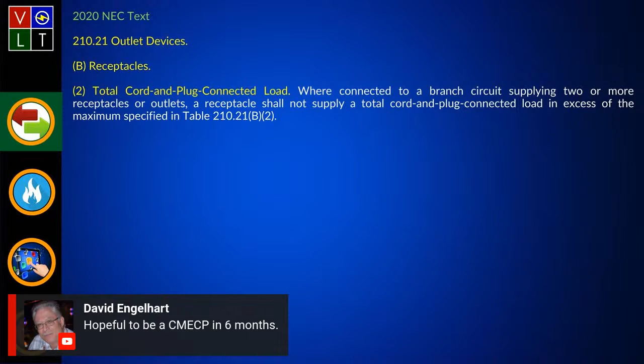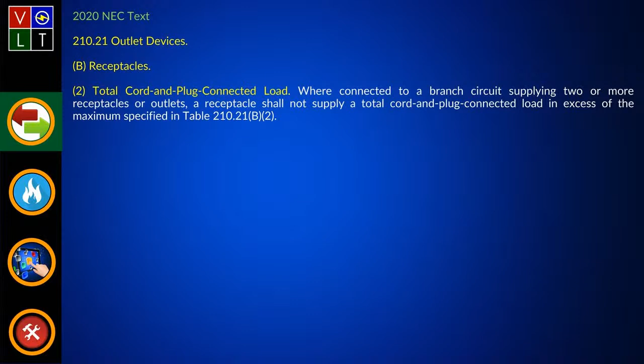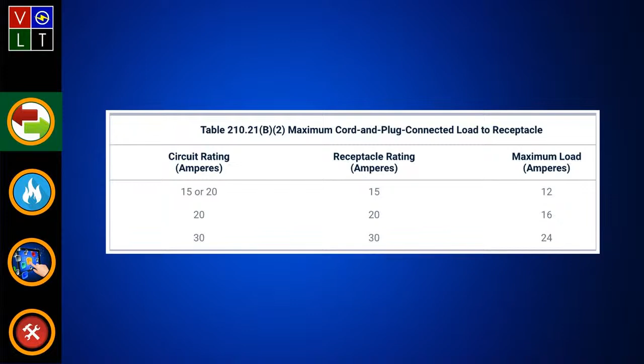What I decided to show here is 210.21(B)(2) and (B)(3). We'll talk about this. If you're talking about cord and plug connected, this is where you have a branch circuit supplying two or more receptacle outlets. It says the receptacle shall not supply a total cord and plug connected load in excess of the maximum specified in Table 210.21(B)(2). This sets up your receptacle rating and the maximum load permitted on each one of them. So if you get into your cord and plug connected.